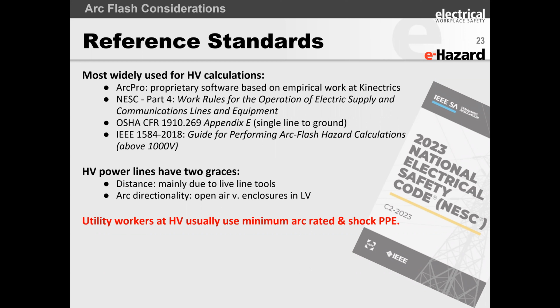Now, the NESC Part 4 also has work rules, several tables that we use for high voltage calculations. So if you have transmission lines, or distribution systems that are more than 15 kV, or even if you are below 15 kV but have overhead lines, it is best to default to ArcPro, the NESC, or the guidelines provided in Appendix E of 1910.269. Now, high voltage power lines have two saving graces for us. Number one, because of live line tools and bucket trucks, they allow us to work further away. That means being further away gives a lesser chance of coming into direct contact with the line and being electrocuted. But also, as you increase distance, your arc flash energy starts decreasing.